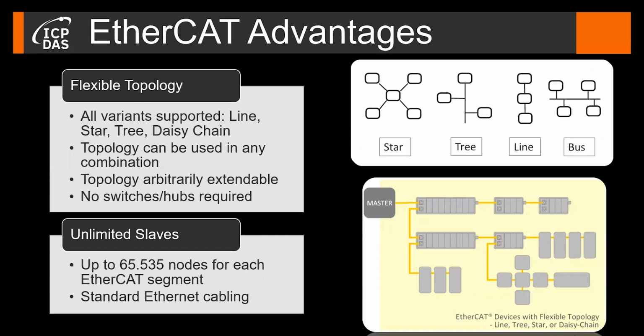EtherCAT is virtually limitless when it comes to network topology. Line, tree, star, ring topology, and any combination thereof are supported. An advantage of the flexible topology is that existing automation machines and equipment can be easily and flexibly extended. In an EtherCAT application, the machine setup determines the network topology and not the other way around. So any topology can be chosen to flexibly adjust the network to meet the machine application's requirements. Moreover, thousands of devices can be connected to an EtherCAT network without the use of external switches, which reduces the cost and avoids restrictions when designing a network.